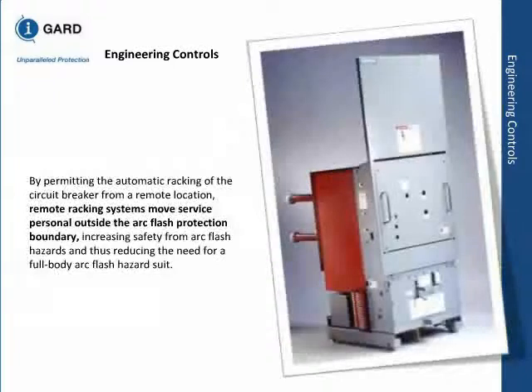You can have remote racking of breakers, since industry statistics prove most faults happen when the breaker changes state or when they're racking in. So you can have a remote racking system so somebody is not there. It does not reduce the hazard, but it does reduce the risk. Equipment may be damaged, but a person may or may not be there to get hurt.